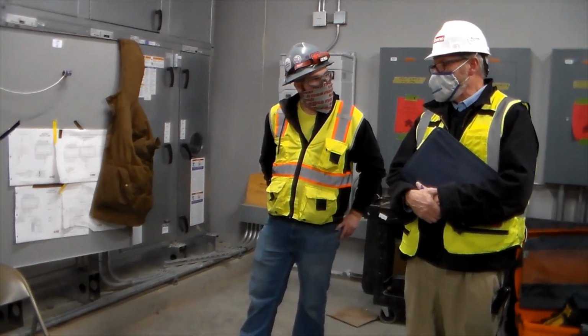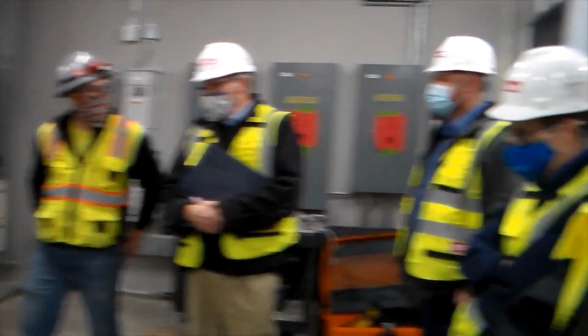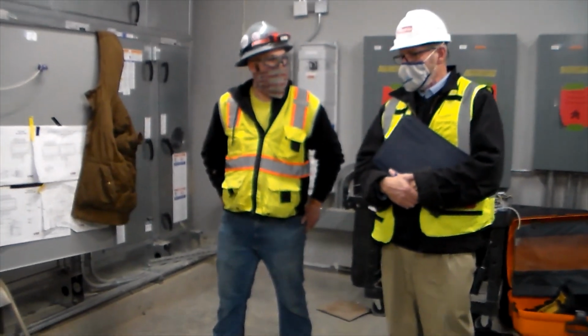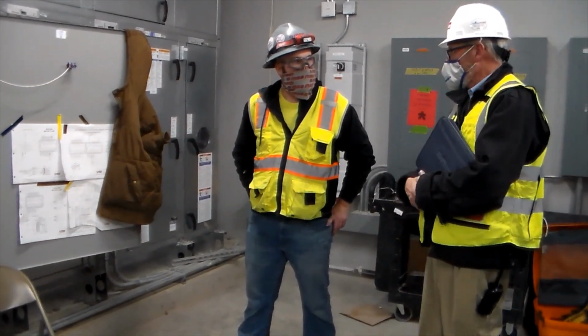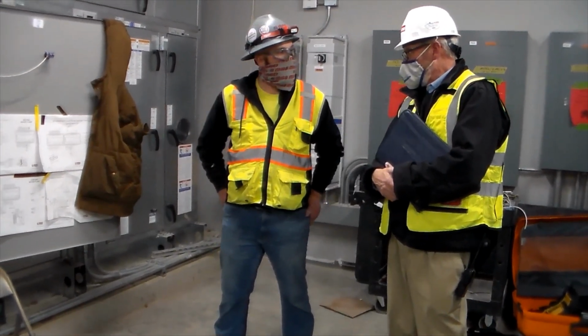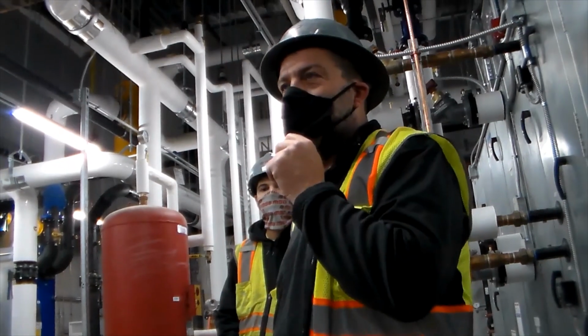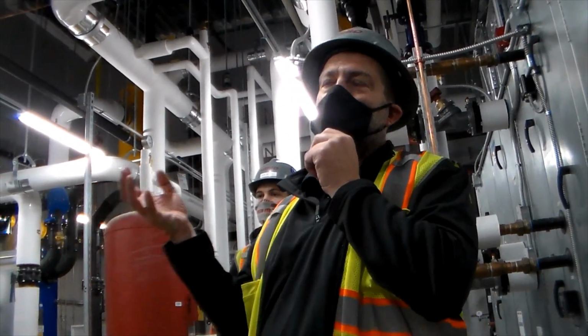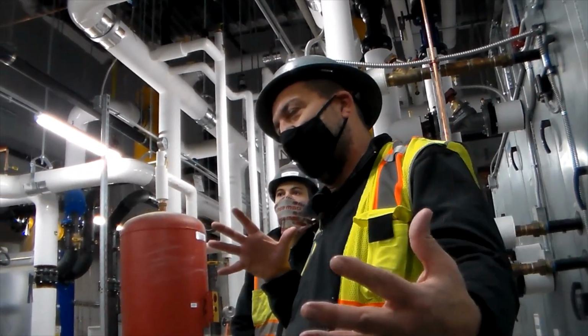At some point, I'm going to ask a question that's going to throw you into the ditch, and I want Randy nearby. We were told that the lighting system will play in the sandbox with this system for the purpose of occupancy. Yes. Now, I want to know how that works, and Randy wants to know how that works. So basically, I spoke with the gentleman that was here to install the lighting system, and over BACnet, he's going to send me commands on what room's occupied, what room's not occupied. So there will be the schedule that basically sets everything up.